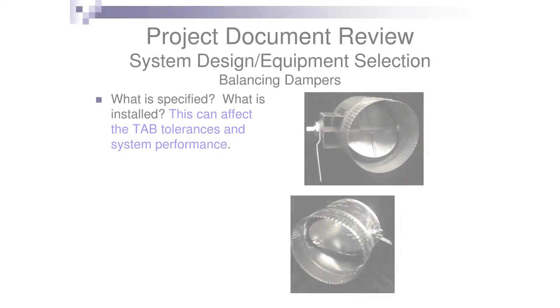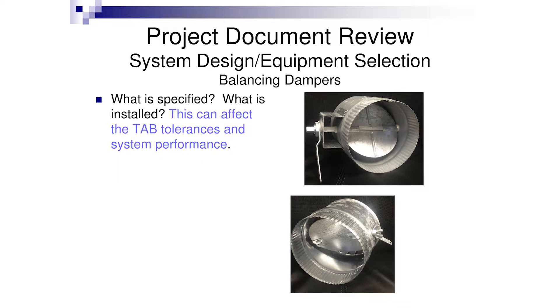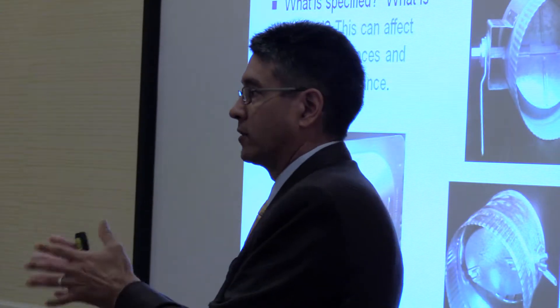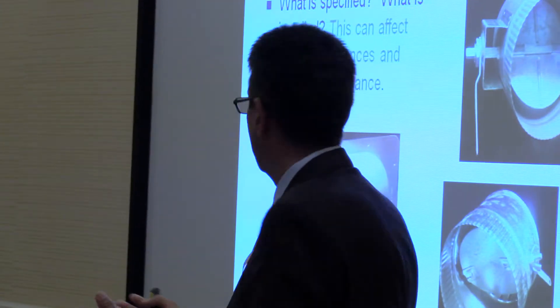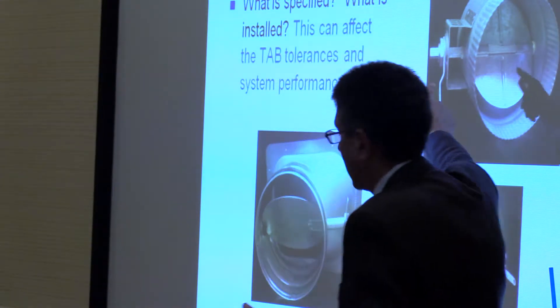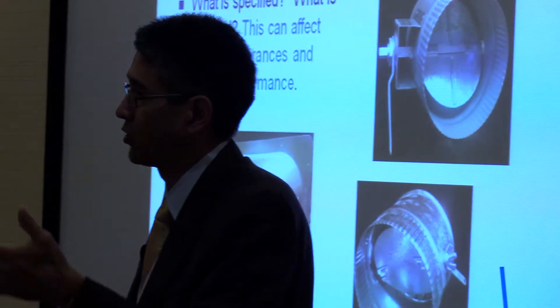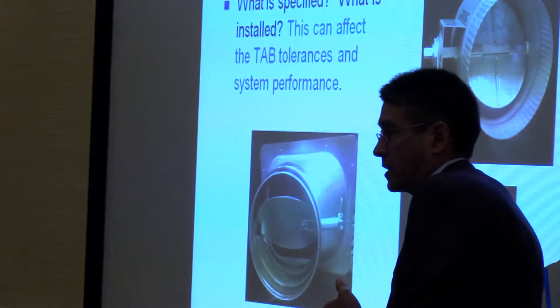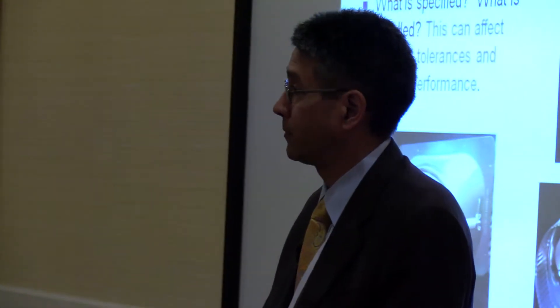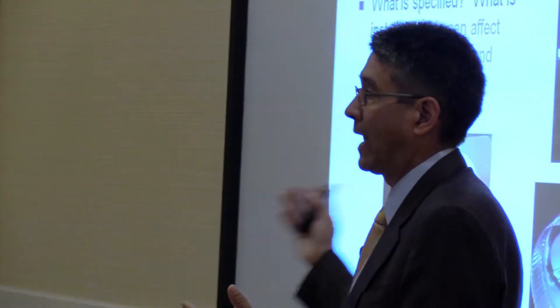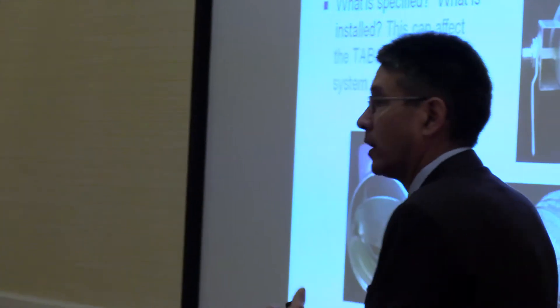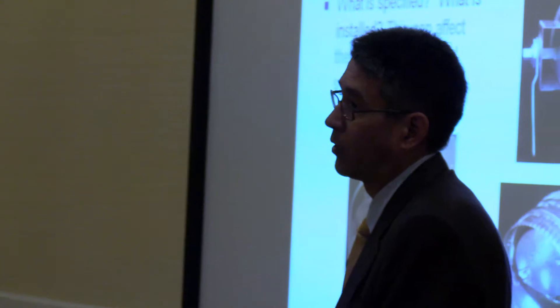For critical rooms, it's more about watching air changes and room pressure — not worrying about plus or minus 5% airflow out of that outlet. When talking about all the different tolerances, we're back to equipment selection and equipment installation. If I have poor quality balancing dampers, it's very tough to get tight tolerances. Make sure good quality balancing dampers are installed so you can lock down handles that are reliable and actually reduce your airflow — we've seen situations with shop-made dampers where you close it all the way and still get 100-200 CFM out.